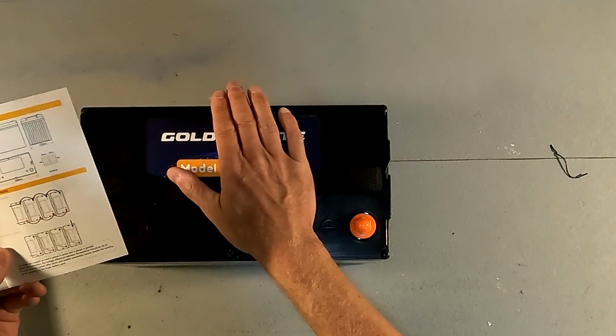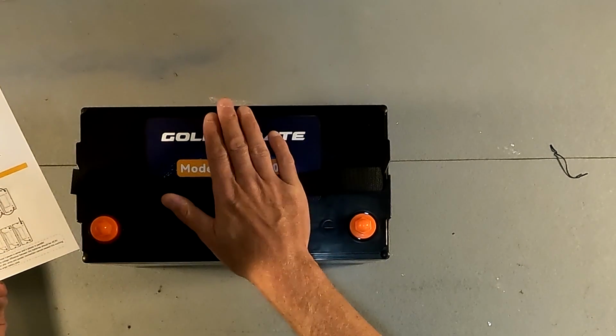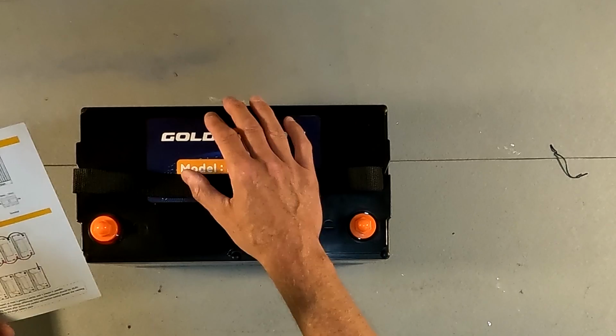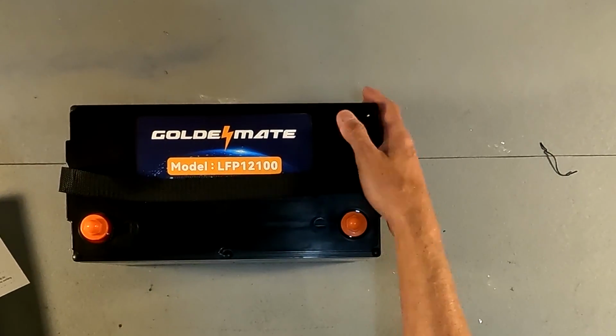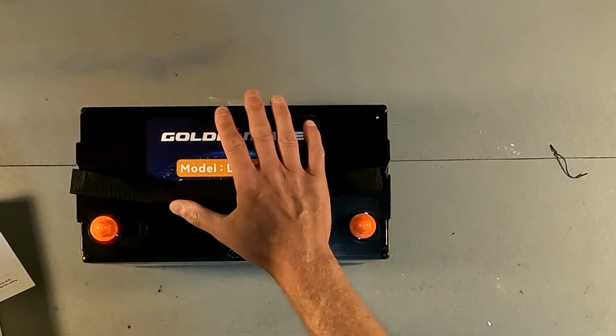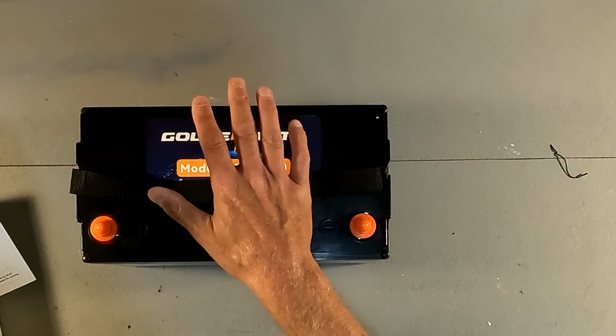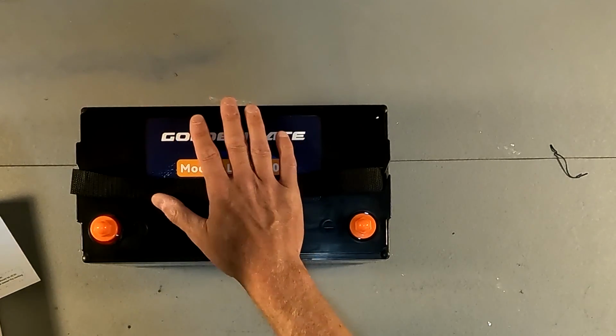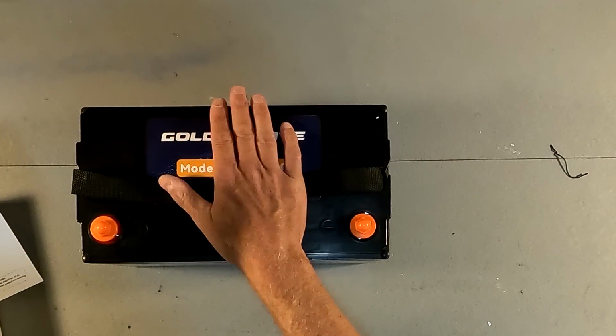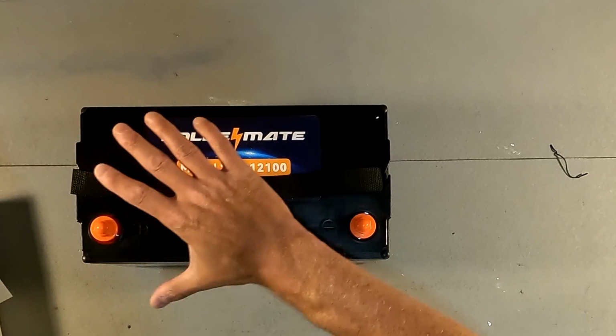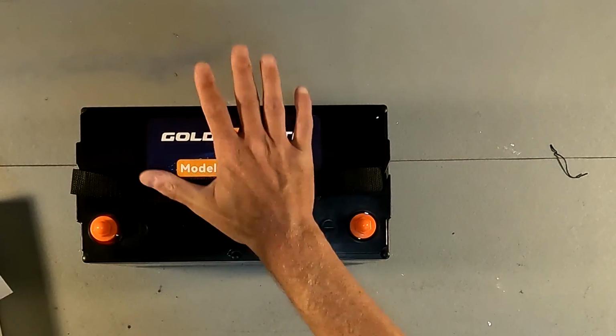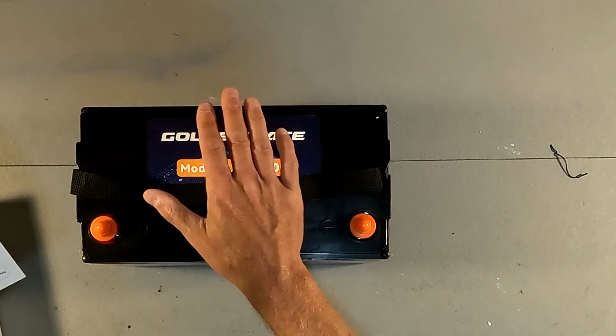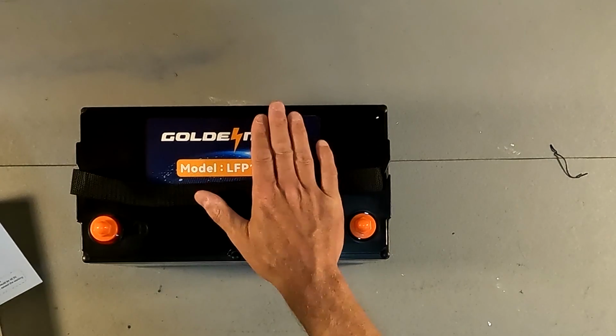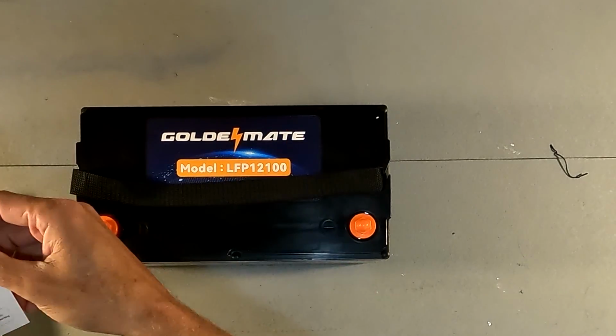It does say that the life cycle on this is 5,000 plus cycles. It does say you can hook up 4 of these in parallel for 400 amps, and you can connect 4 in series for a 48 volt 100 amp hour battery. Then you can combine all those together. If you had 16 of these batteries, you could possibly have a 48 volt 400 amp hour battery.